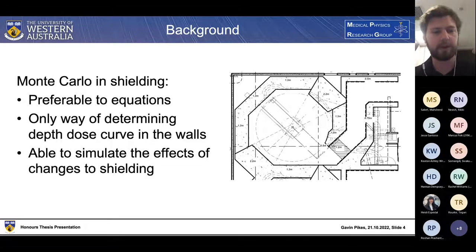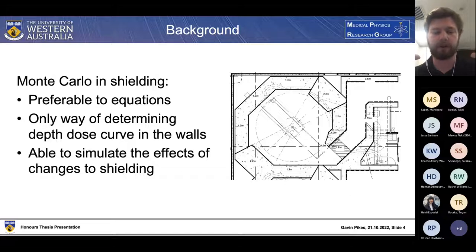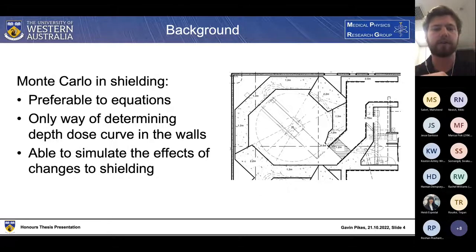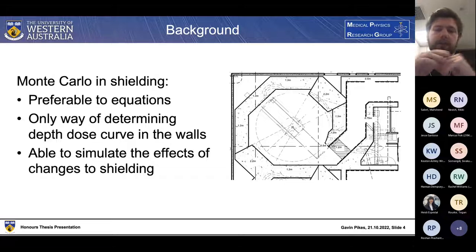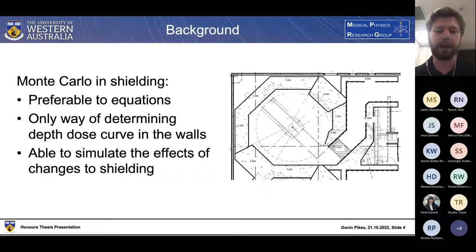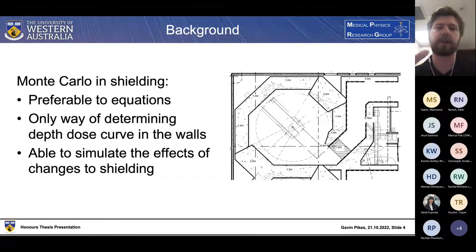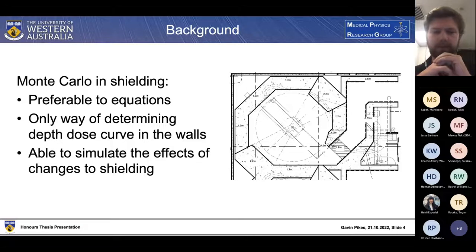Using Monte Carlo simulations, we can instead provide a much more individualised analysis of bunker shielding capabilities. Monte Carlo simulations are also the only way of determining depth dose curves within the walls of the bunker — we can't drill a hole in the primary barrier and place an ionisation chamber there. Monte Carlo is really the gold standard for determining how energy is deposited within the bunker walls, and allows shielding changes to be simulated and analysed without physically implementing them, which is obviously more cost effective.